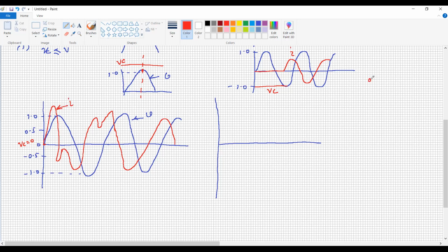What is our circuit? The circuit comprises a static capacitor which is connected in shunt. So it is a shunt compensation in the system. Bidirectional valves are there, and with the help of the bidirectional valve, we have connected one inductor to limit the current or to avoid resonance. See, this is the current which is going to flow over this one. This is the thyristor switch. Okay, and this is the inductor, and the system voltage is V.